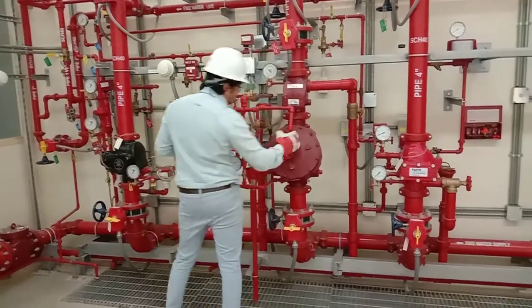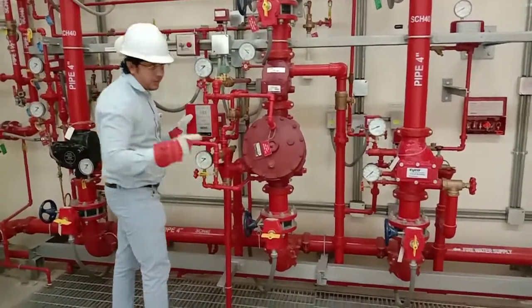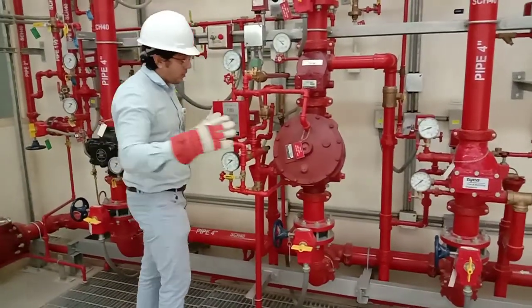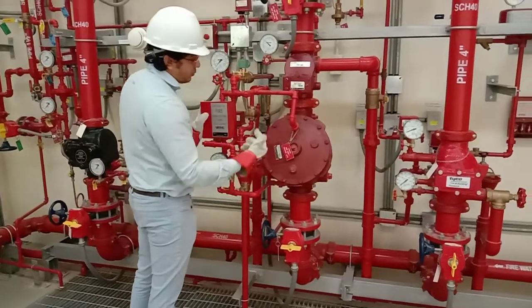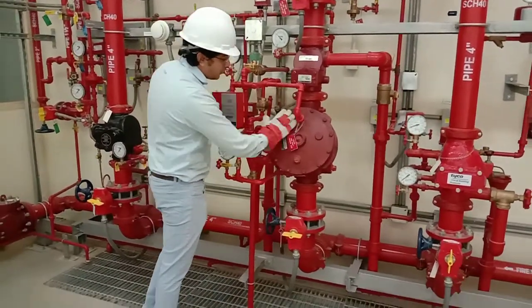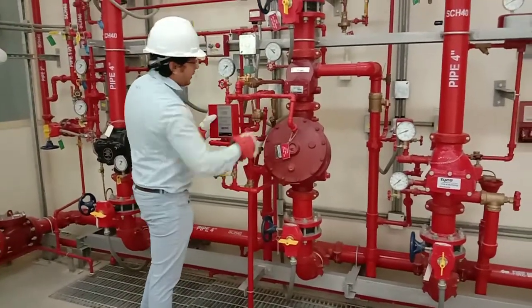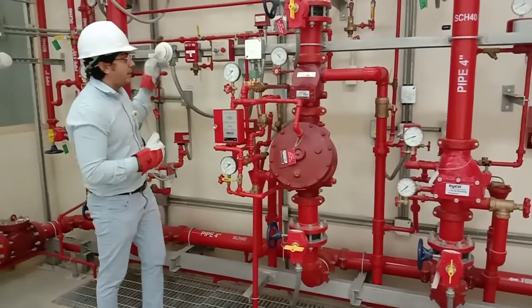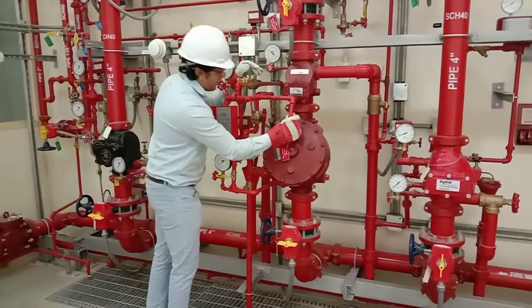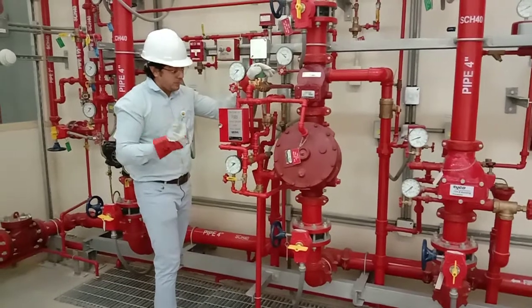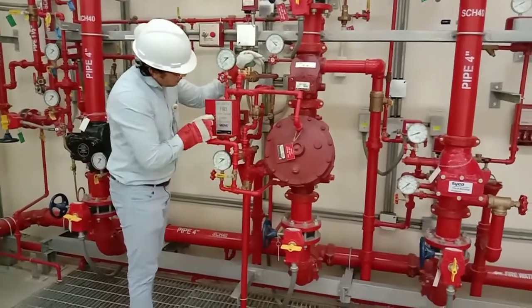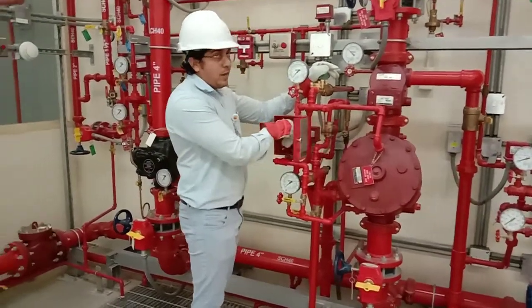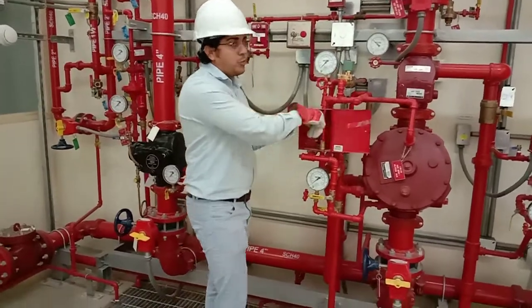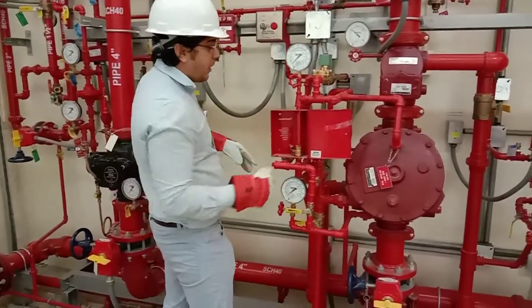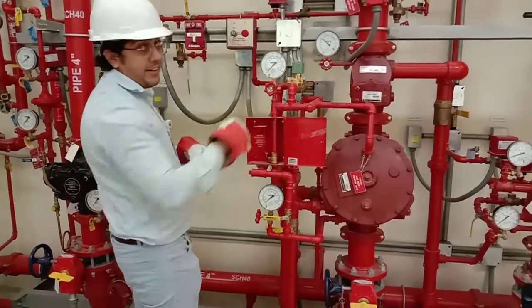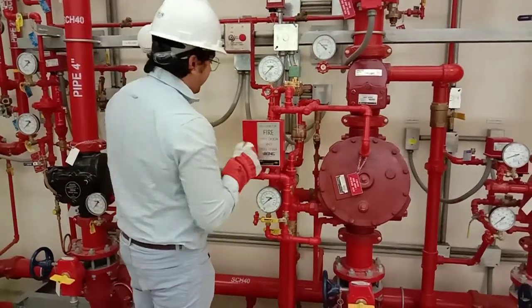Now again, this is pressurizing the sprinkler rubber, the one we discussed. The inside elastomeric rubber will close the inlet line to the outlet line until there is a detection from the fire and the solenoid valve is open. We have some other options to open this one. We have a manual pull lever, right? So if you want to open it manually, just push it and pull it down and it will be activated. Just turn 90 degrees so that it will be active.